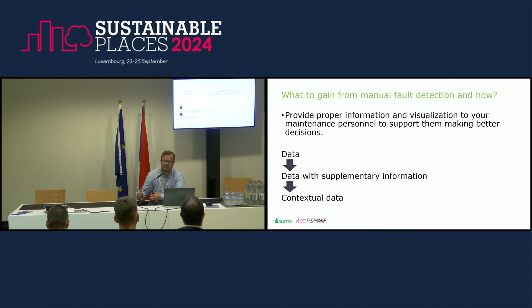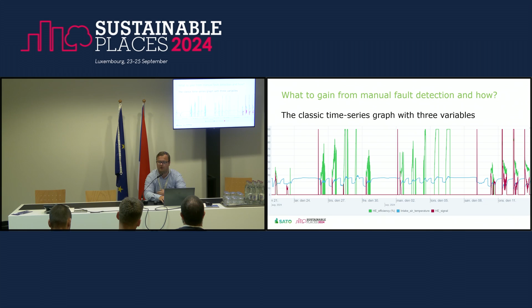If we look at the classic version, here you see a time series graph. This could be a version of how you could assess if the heat efficiency of a rotary heat exchanger is actually good. Normally we know above 80% is not that bad. But that raises the question: should it be 80% all the time, or are there times where we shouldn't actually have high enough efficiency? As you see here in the green curve, it's not that easy to assess if it's actually performing well under the conditions it's performing under.